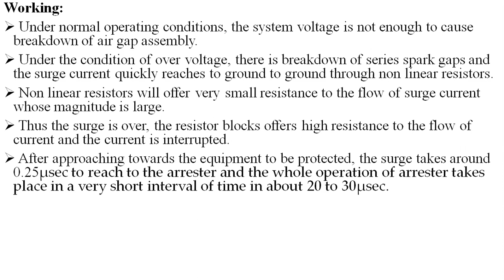After approaching towards the equipment to be protected, the surge takes around 0.25 microseconds to reach the arrestor, and the whole operation of this arrestor takes place in a very short interval of time, about 20 to 30 microseconds. The arc is extinguished at first current zero by cooling and lengthening of the arc, and also the voltage and current are almost in phase.